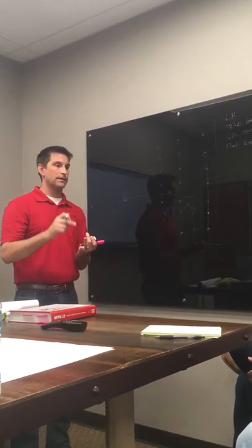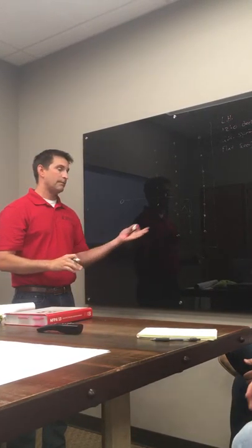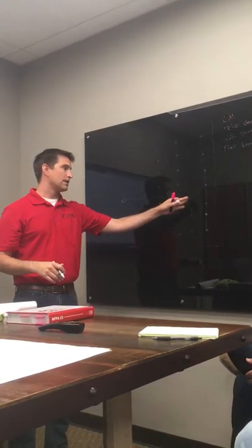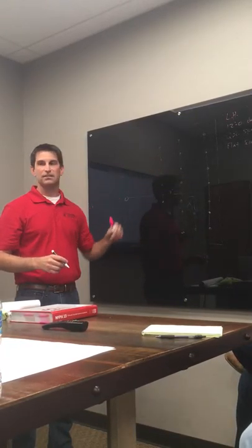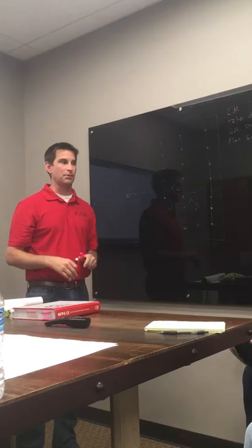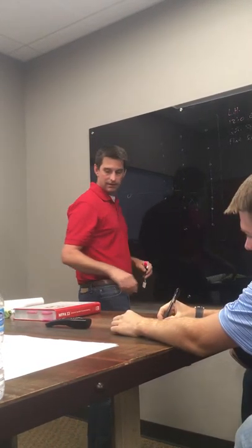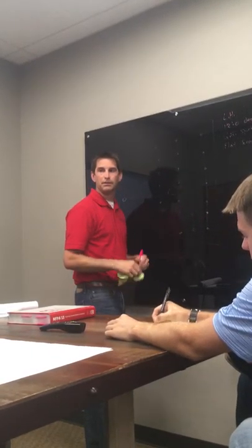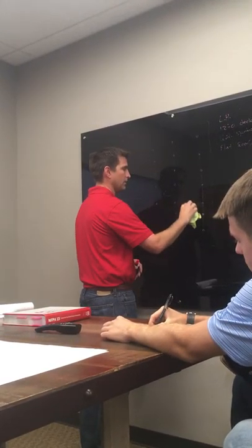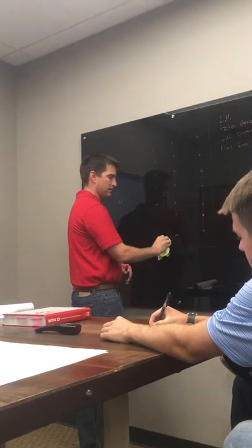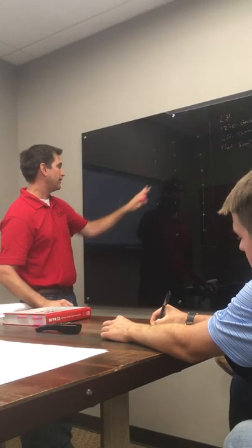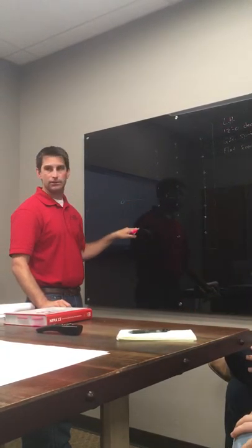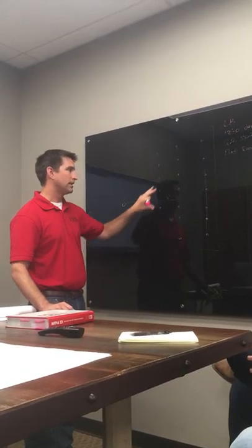That extra size of hanger rings, that extra size of branch lines. And then my field guy's got to dig through more pipe to find those specific things. And all that extra work versus keeping it all 2-inch is to just be consistent and keep it simple. Yeah. Simple is smart. And it helps make it easy to count. So that would be one reason, but there's a million different reasons that it could be more challenging. You may need more areas. A lot of it usually will be hazards, right? I have light hazard over here, and I have ordinary hazard right here. Light hazard isn't going to prove ordinary hazard worse, so I got to do 2 calcs just because of that. Even though this is closer, that still doesn't prove that more.